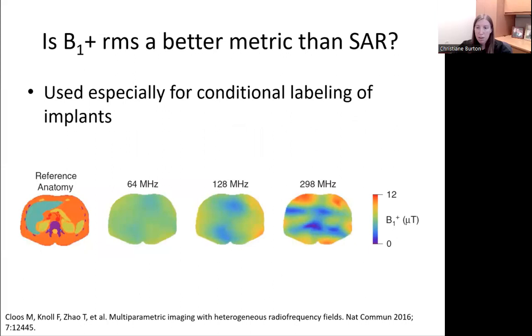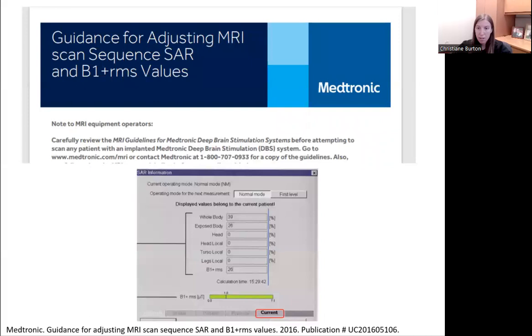It should be noted that actual B1 and B1 plus vary by location inside the subject and are determined as spatially average values within an axial center slab. The error in this estimation may be substantial, particularly if an implant is present. In fact, the major use of B1 plus RMS metric is for the conditional labeling of implants. Implant manufacturers are responsible for determining the maximum B1 plus field compatible with safe use of their device in the MR environment.